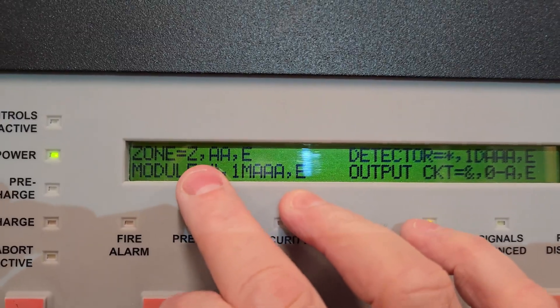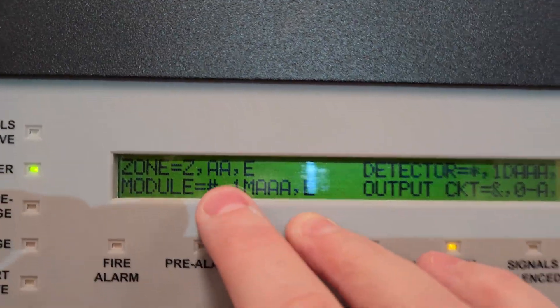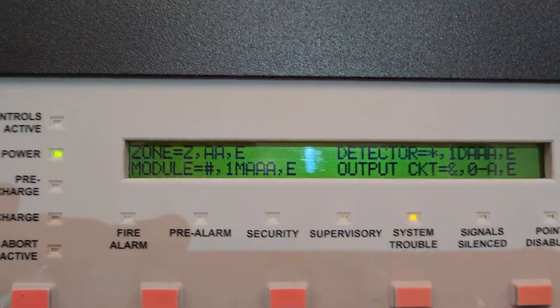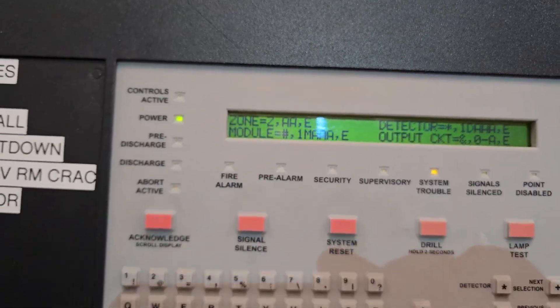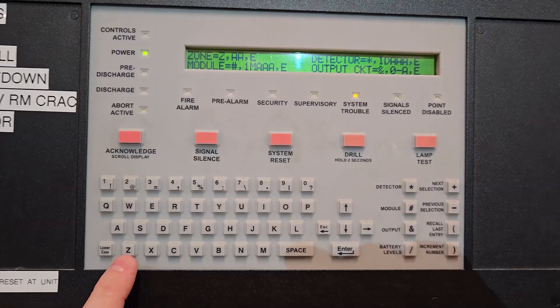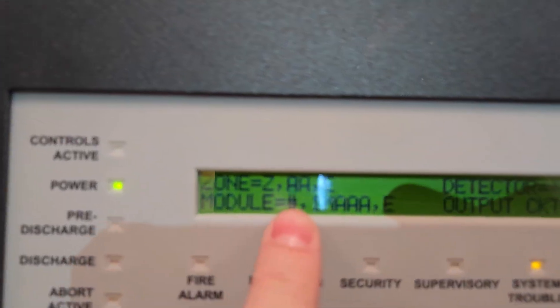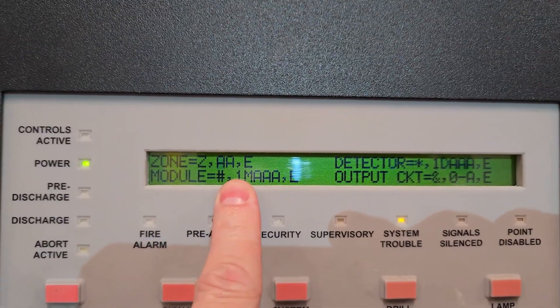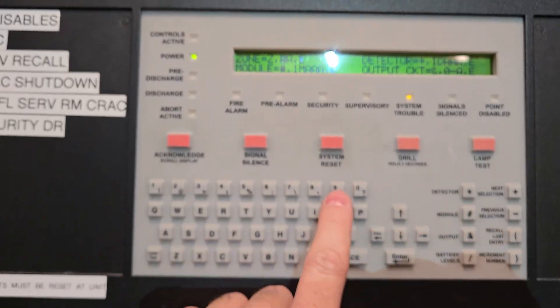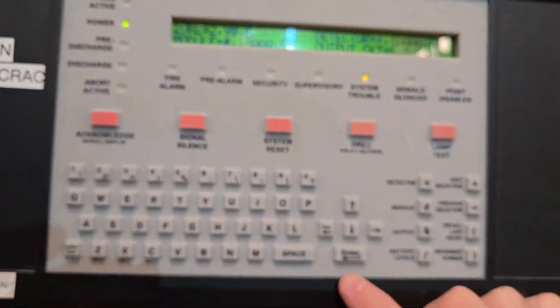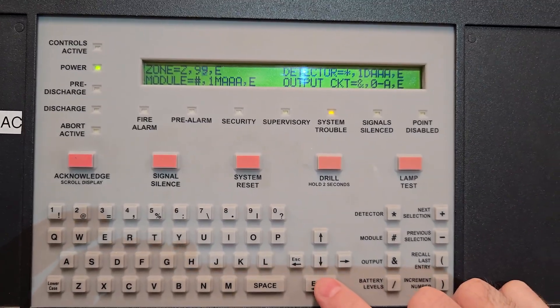After hitting Z, you see a flashing symbol on the screen. The display shows 'Z comma AA comma E' — the two A's mean it's waiting for a two-digit number, and the E just means Enter. So I hit the Z button and now the first A is flashing, ready for input. Since it's zone 99 I'm going to hit nine, nine. Now it's flashing 'zone 99 E' — the E again means enter.